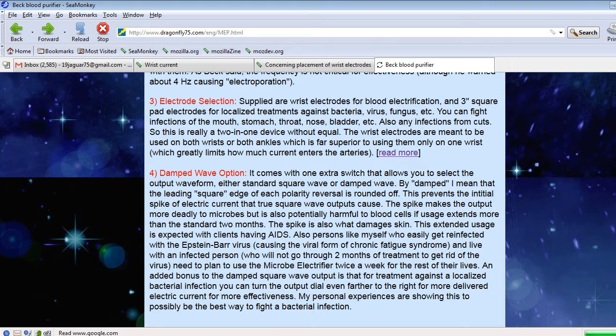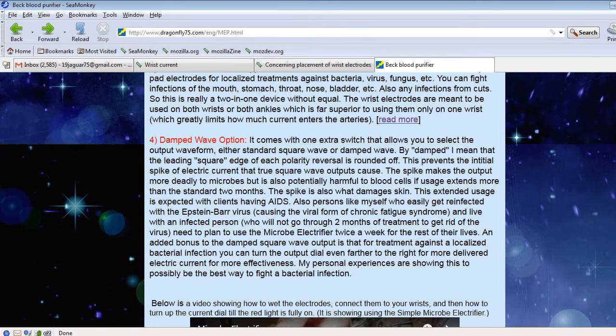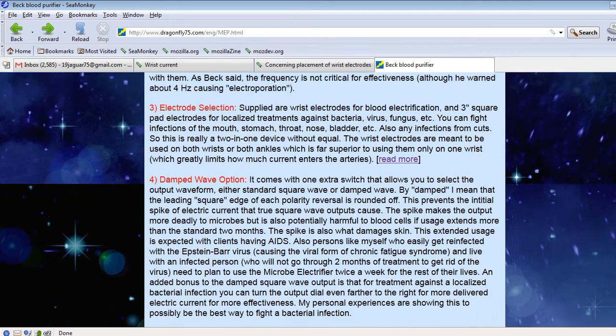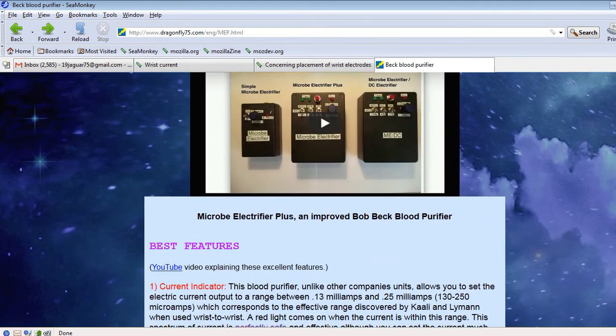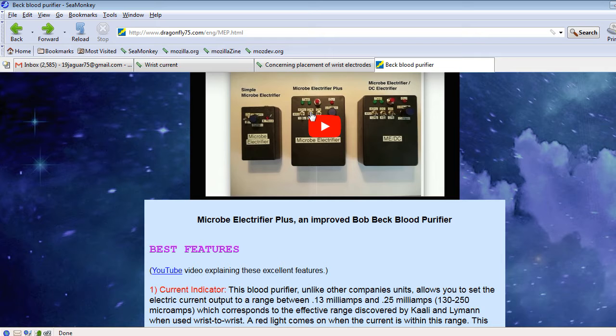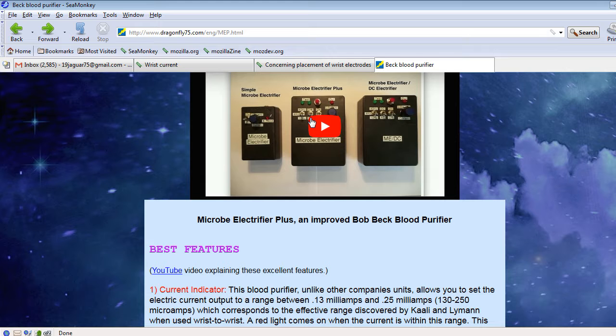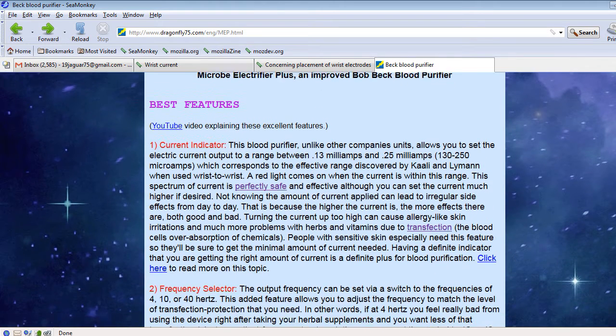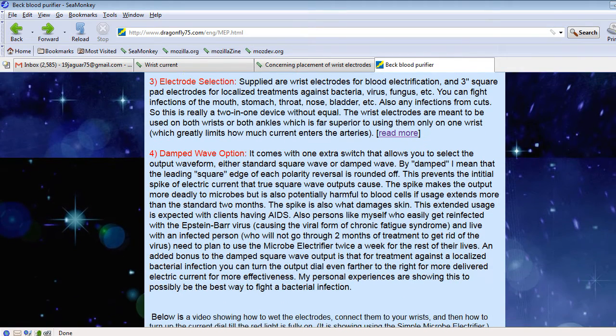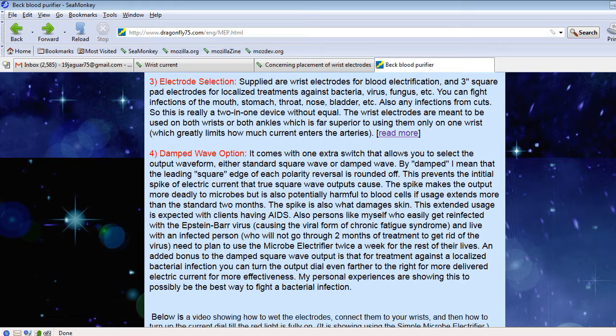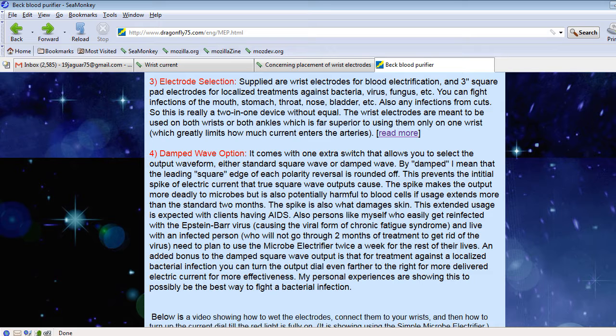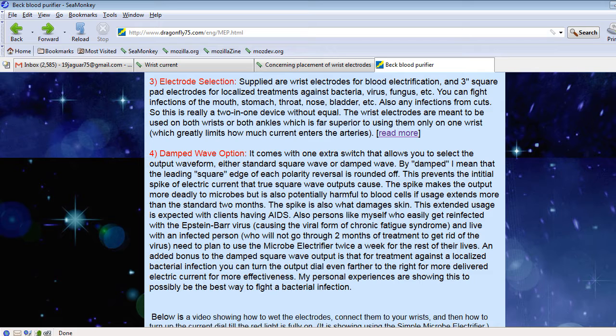So last but not least is the damped wave option. There is a switch on the device that says DW and SW. DW stands for damped wave and SW stands for square wave. That modification basically takes the squareness off of the transition between one polarity and the other. Because what the device is doing is switching polarity so many times per second. And each time it switches polarity, you get a spike of current. And so by including a capacitor across the output circuit, when you select the DW option, the capacitor absorbs a lot of that spike of current so it doesn't go through your blood.